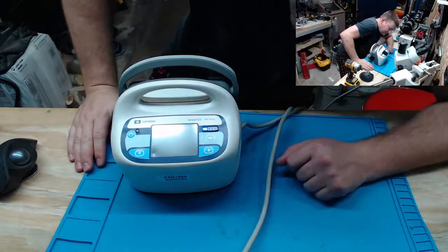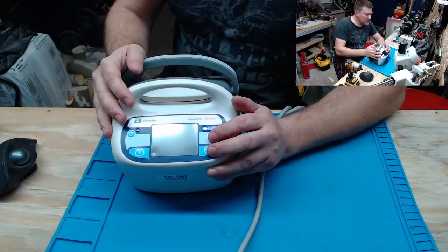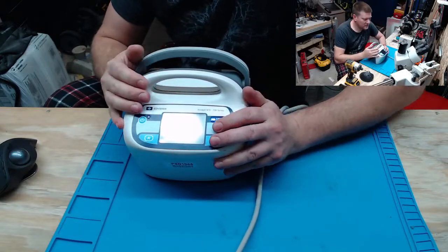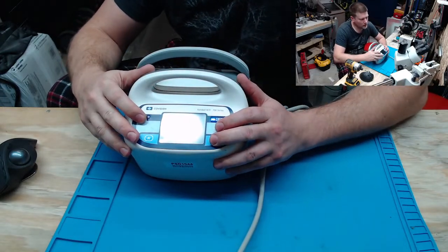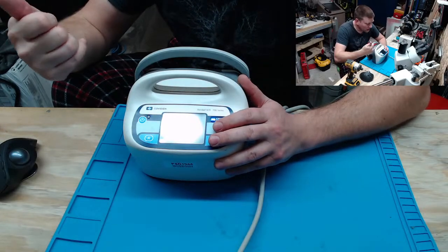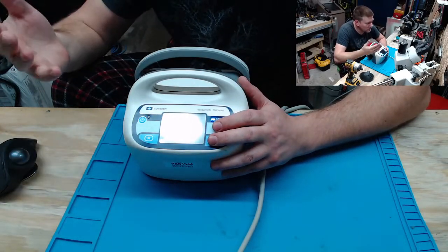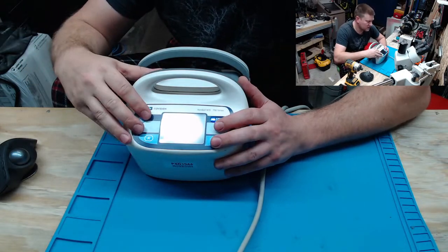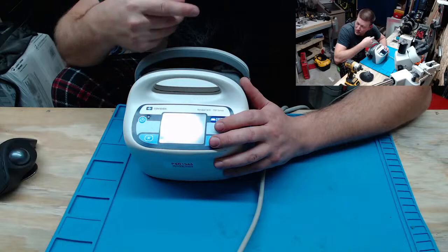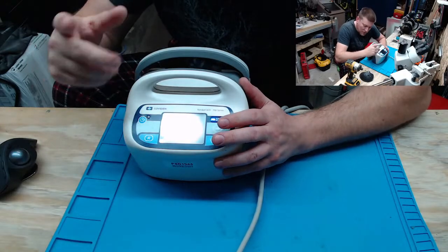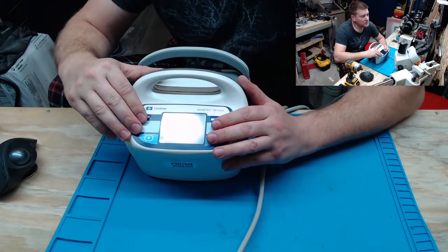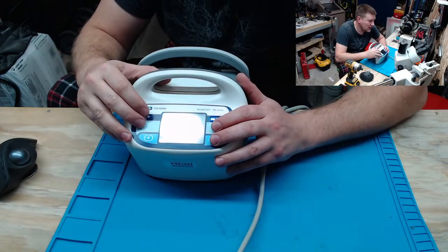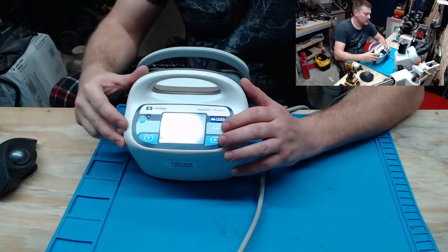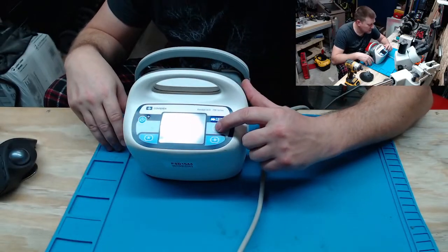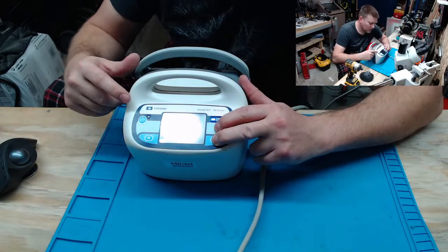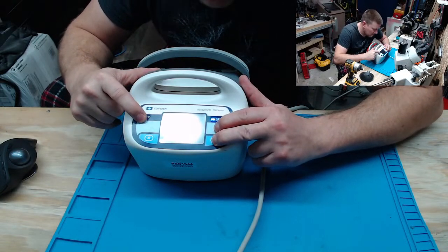All right, anyway. There's a hidden menu that you can access on these. So if you ever have error codes, like it gives you pressure alarms or no pumping alarms, or if you turn it on and you don't hear the valves clickety-clacking or the motor turning, then you go in the service menu and you can do a function check and a burn-in test. I'll show you what those are. There's a forward arrow and a B. So I hold down both of those and I turn the device on.